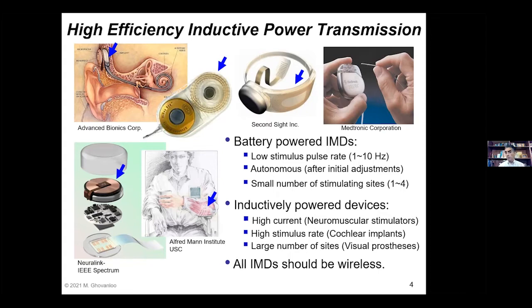For example, a pacemaker operates at a rate of 1 to 10 hertz, which is basically the normal heart rate. As a result, the power consumption of these implants, if you average it out, is in the microwatt range. So when the power consumption is in the microwatt range, the primary battery, which is not even rechargeable, can last between 5 to 10 years, and there's no need to recharge these batteries.